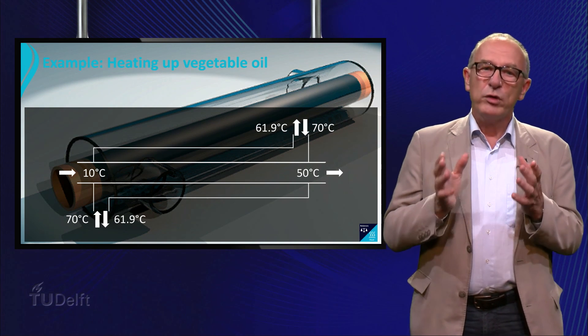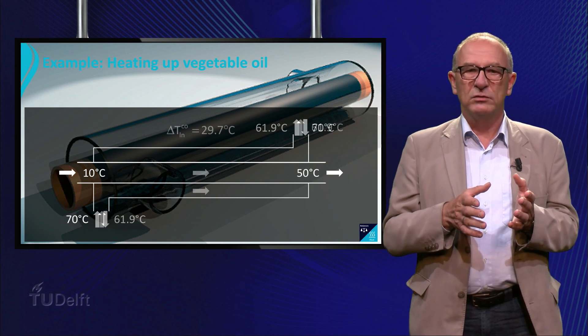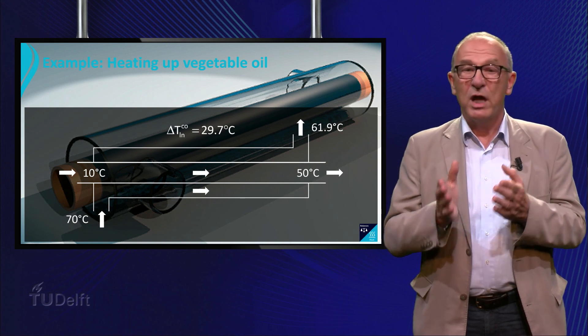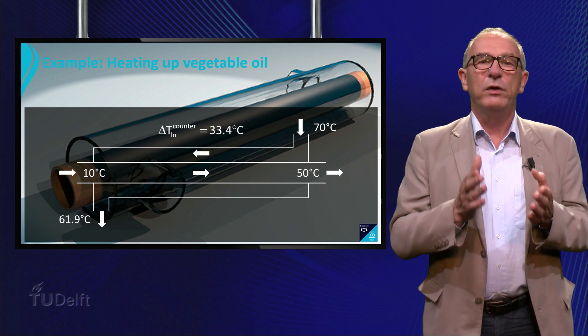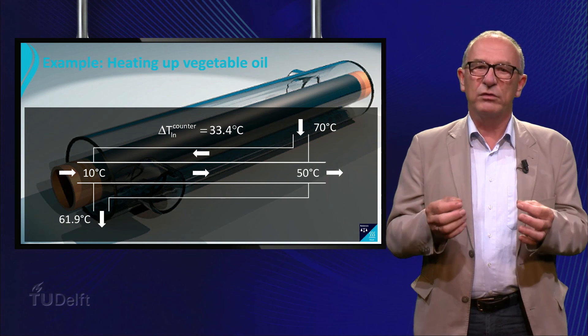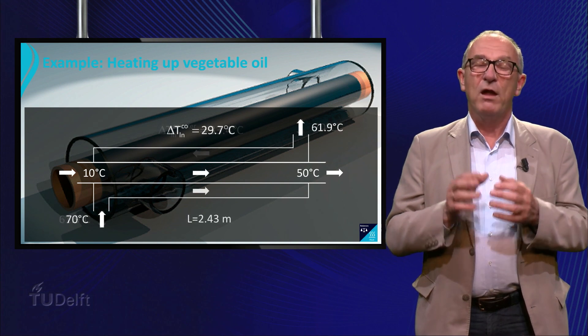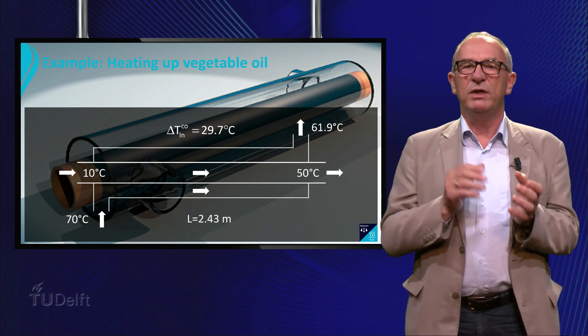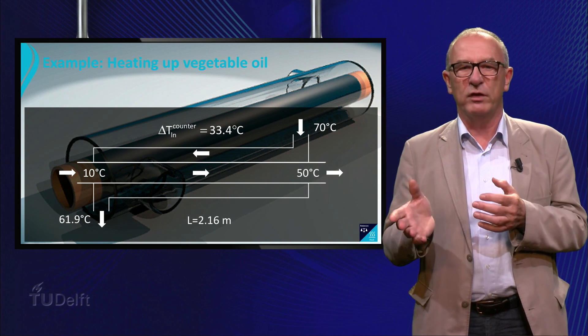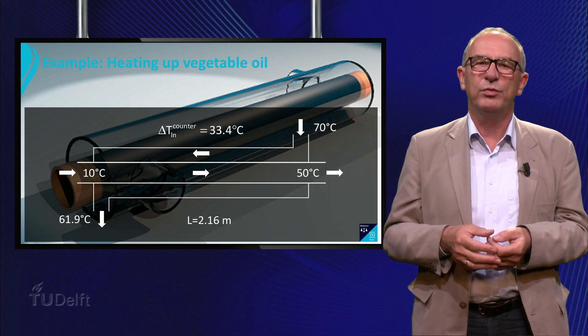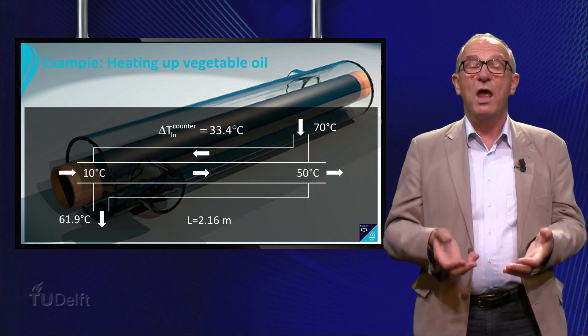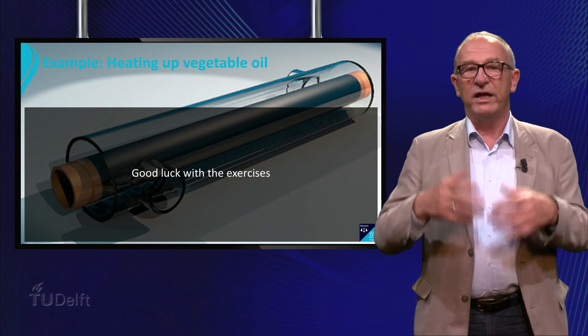Subsequently, we calculate the logarithmic mean temperature difference for both situations. For co-current flow delta TLM becomes 29.7 degrees Celsius, and for countercurrent flow 33.4 degrees Celsius. The larger temperature difference shows that countercurrent is more effective than co-current. Finally, we need 2.43 meters to heat up the oil co-currently and 2.16 meters for countercurrent flow. This is an example for one tube, but it illustrates how you can design the size of a heat exchanger with the knowledge learned in recent weeks. Good luck with the exercises and thank you for your attention!